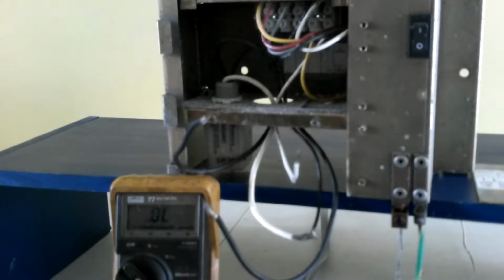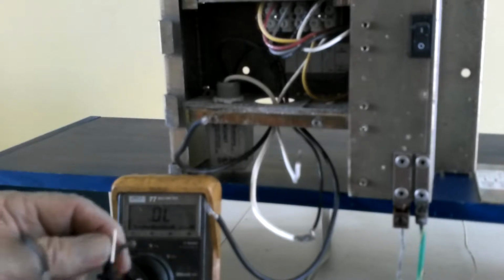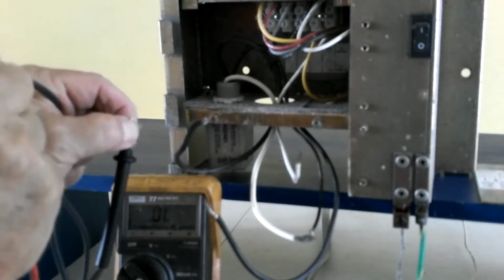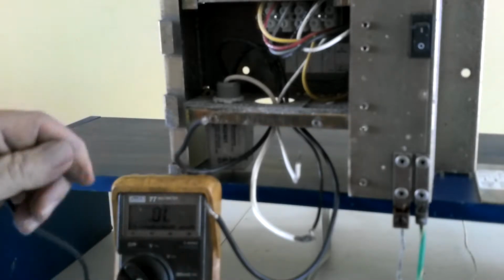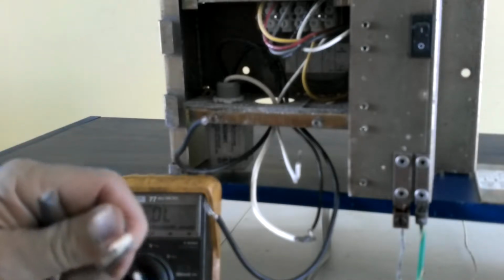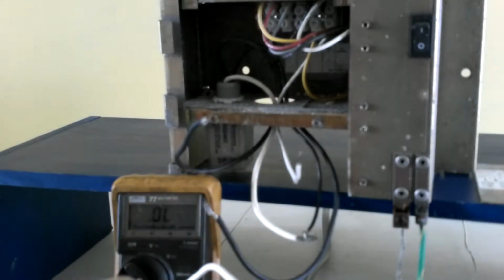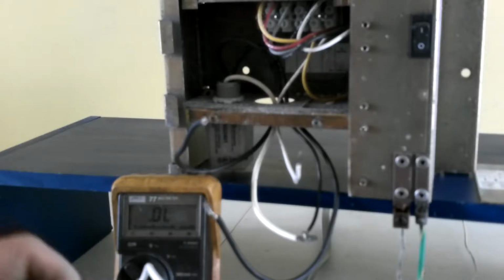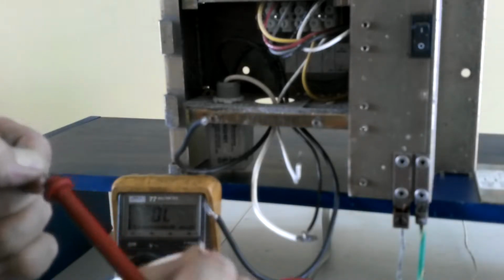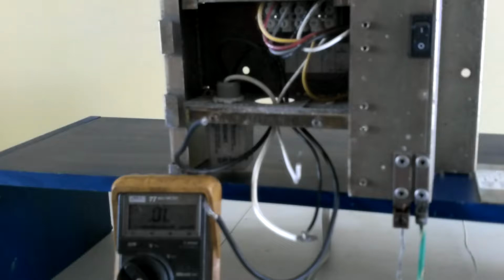If you need to check the surge arrestor to make sure that it is okay, what you want to do is use a voltmeter set to read for continuity, as we've set here. Take one of your voltmeter probes, connect it to one of the 2 black wires, as we have done here and here, and you'll notice that the meter shows no connection. That is what it should be. Next, use the probe, and you want to connect one probe to your white wire, one probe to the black wire, and again you'll notice that there is no connection. Next, connect the white wire to the other black wire with the probe, and you'll notice again that there is no connection. That says that the arrestor is good to use.